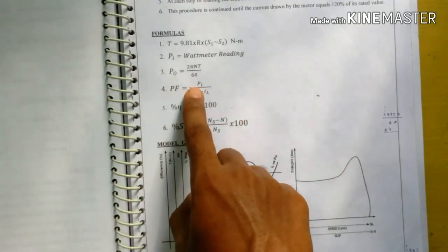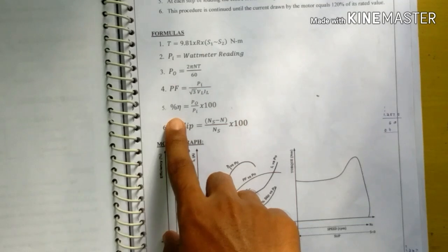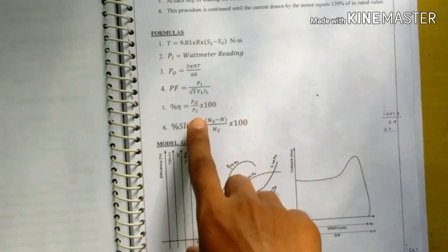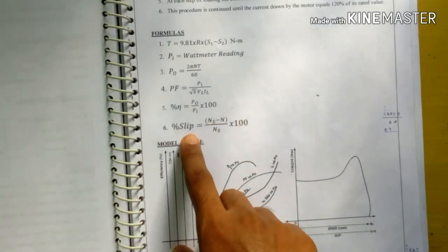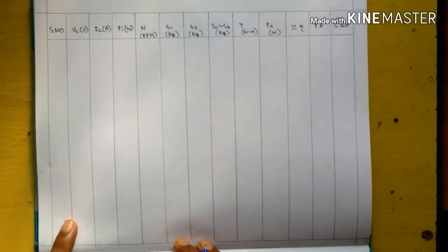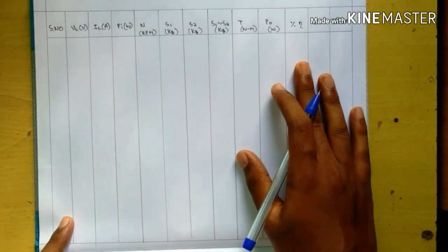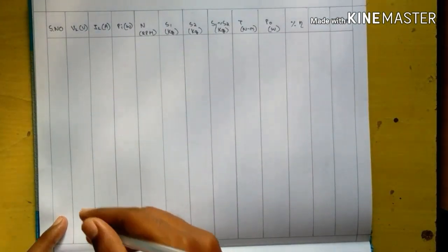Power factor is Pi divided by root 3 into VL into IL. Percentage efficiency is output power divided by input power, that is P0 divided by Pi into 100. Percentage slip is equal to (Ns minus N) divided by Ns into 100. Now the tabulation for this experiment will be filled in with the readings of voltmeter, current, and wattmeter.